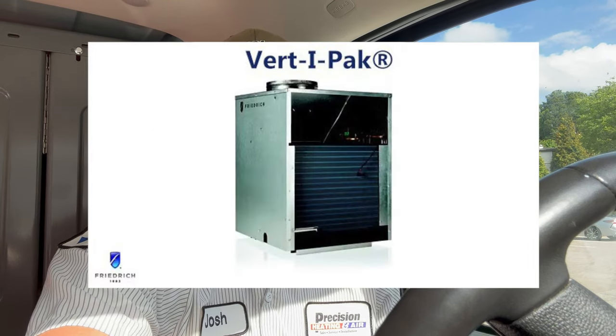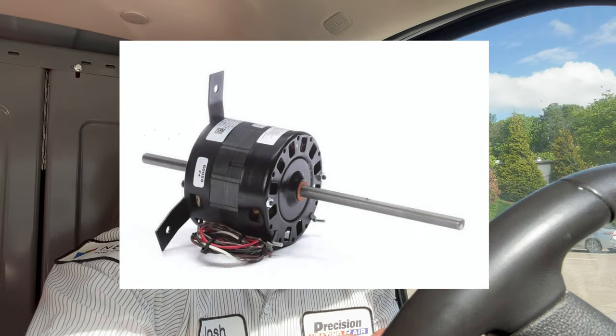All right, so we've got a little bit of a different type of unit we're working on today. This is a Friedrich Vert-I-Pak — similar to a P-TAC but it stands vertical. I'm going to have to replace a dual motor, which is one motor with a shaft coming off both ends. It runs the condenser fan and the blower wheel. We're also replacing the blower wheel because it had broken into a million pieces. Something you don't see every day — let's get started.